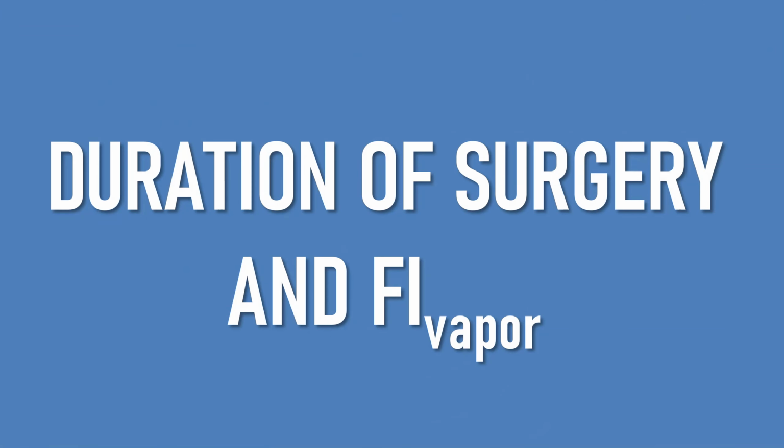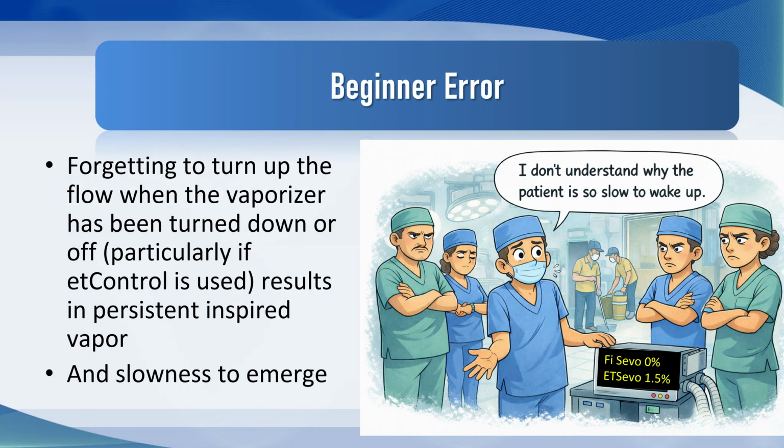Now let's look at the duration of surgery and the inspired concentration of vapor. The biggest beginner error that I see in anesthesia is forgetting to turn up the flow when the vaporizer has been turned down or off, particularly if end tidal control is used. This results in persistent inspired vapor and slowness to emerge.